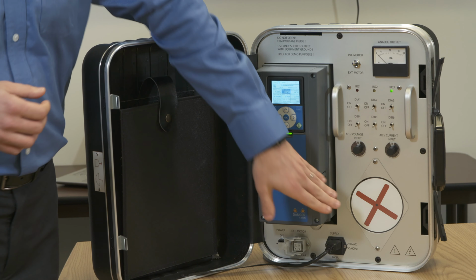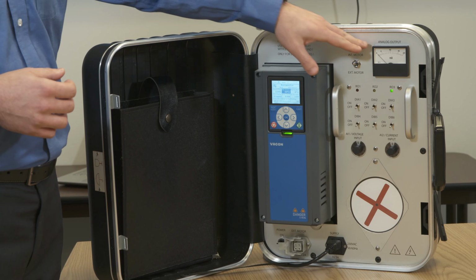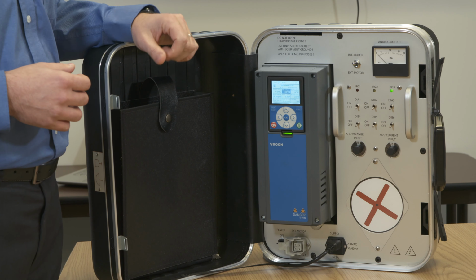So this is the VACON 100 flow demo. I wanted to show you the different parts of it. This is the drive itself and the keypad. This is the digital inputs that we have, 6 of them. We have a couple of analog inputs here, a motor that will be spinning shortly, and an analog output gauge here. On the keypad, on the screen, I want to show you what it's programmed for so that when we run it, you'll understand how the keypad works and what it shows.